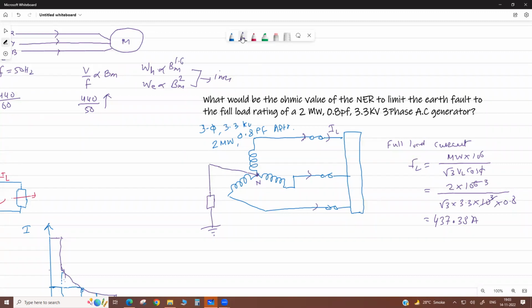Now, my dear, suppose in this system an earth fault occurs, meaning any line becomes earthed. In this case, it makes a circuit through the nearest earth point, and the current starts to flow from this particular phase to ground. That is your fault current. This fault current flows through the neutral. Now it is very high. So we limit this earth fault current, which is similar to a short circuit current, up to the full load current.